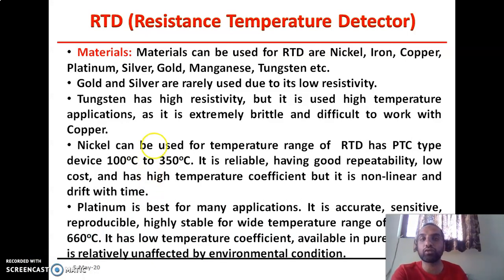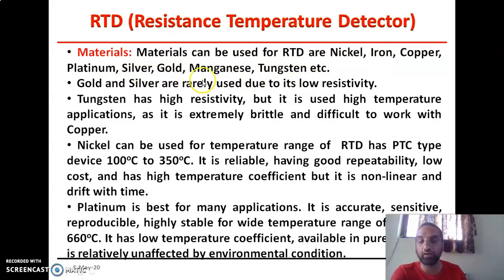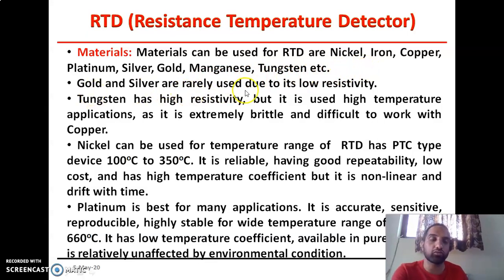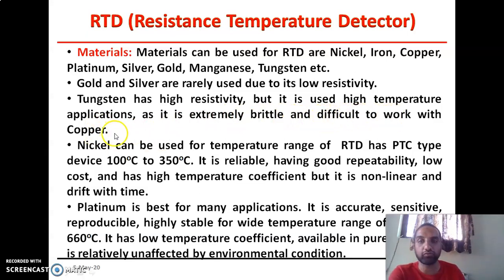Materials that can be used for the construction of RTDs include nickel, iron, copper, platinum, silver, gold, manganese, tungsten, etc. Amongst all these materials, gold and silver are rarely used because of their low resistivity. Tungsten has high resistivity and is used in high-temperature applications, but it is extremely brittle and very difficult to work with, so tungsten is not used in the majority of RTD applications.